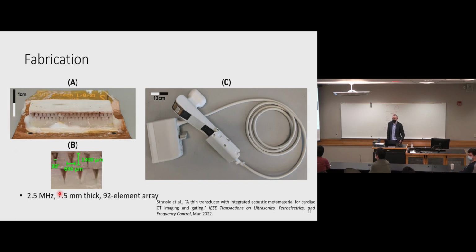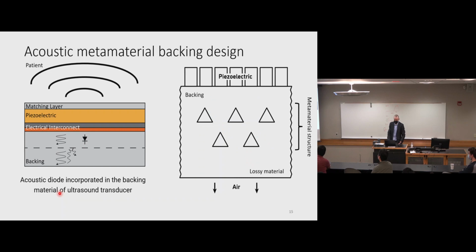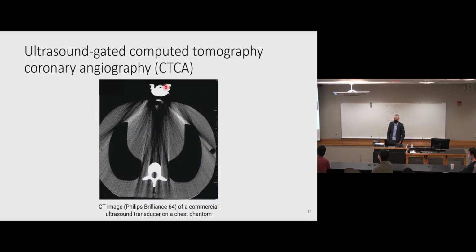And what materials are acceptable in the CT not to create that artifact? Right, so CT is imaging density for the most part. And so if you have something that has a density similar to bone, that's not ideal, but it's okay because obviously we have all kinds of bones in our chest. What we found, and I think this is on one of the next few slides, is that if you use the conventional ultrasound transducer like I showed earlier, this thing has an acoustic backing that's something like 10 times higher density than bone. And so that's why it gives us this really terrible artifact. But if we can get it down like an order of magnitude or so and get it close to bone, then it's better and it could be acceptable.